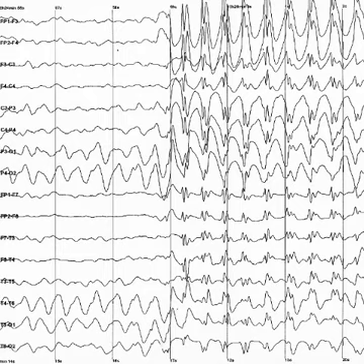Each electrode is connected to one input of a differential amplifier. A common system reference electrode is connected to the other input of each differential amplifier. These amplifiers amplify the voltage between the active electrode and the reference typically 1,000 to 100,000 times, or 60 to 100 dB of voltage gain. In analog EEG, the signal is then filtered, and the EEG signal is output as the deflection of pens as paper passes underneath. Most EEG systems these days, however, are digital, and the amplified signal is digitized via an analog-to-digital converter, after being passed through an anti-aliasing filter.